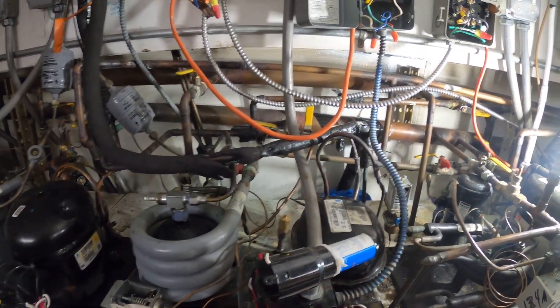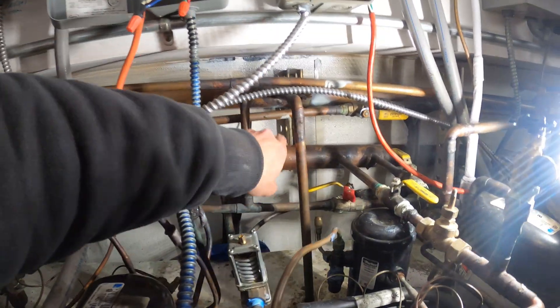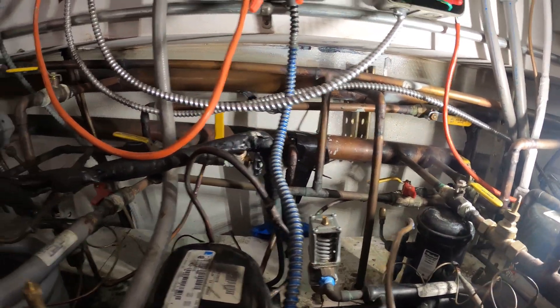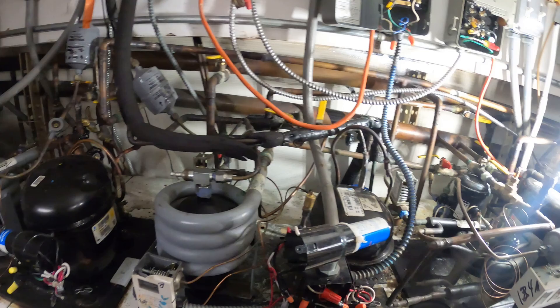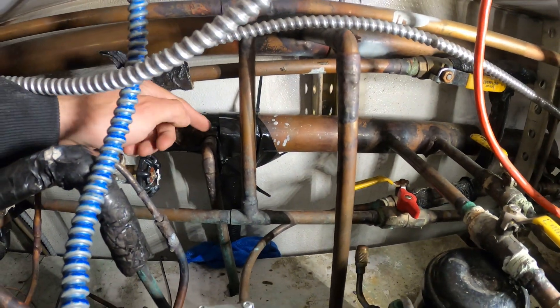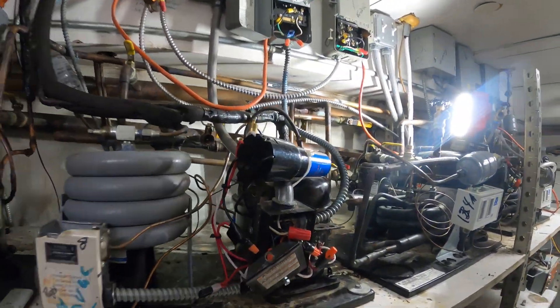What's going on is we have a supply and return — these two large pipes for our cooling tower. These are all water-cooled refrigeration units. In order to make this repair, everything is going to have to be shut down. This pipe right here is leaking. They wrapped some tape and a little hose that leads into a drain — that's a wet vac hose catching the water.